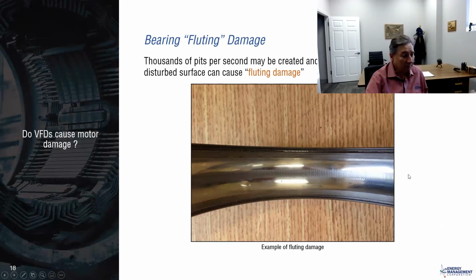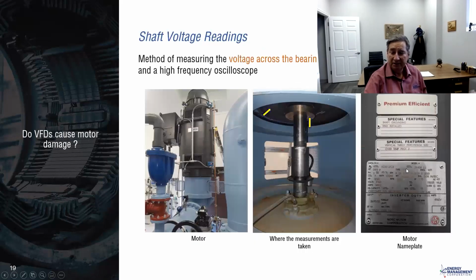On our motor electrical machine rebuilds, it's common practice for us now to cut apart every single bearing. That obviously is not done by a lot of facilities, but we've seen enough of this now that we always cut the bearing and look for this. It's not nearly as prevalent in the early stages. This is just a graph that shows you can actually measure the shaft voltages by putting a fiber brush on the shaft and then on ground. And we do have some graphs of that.